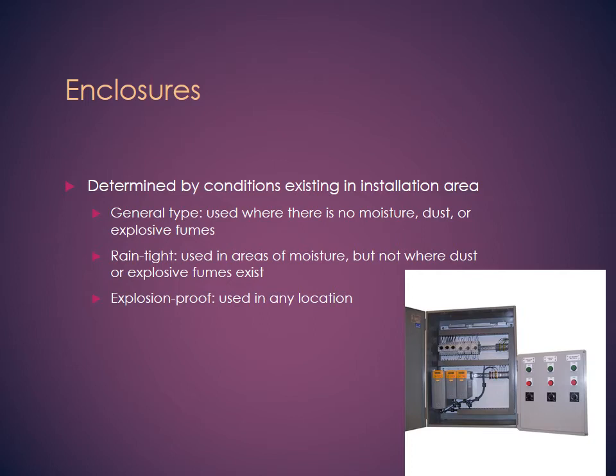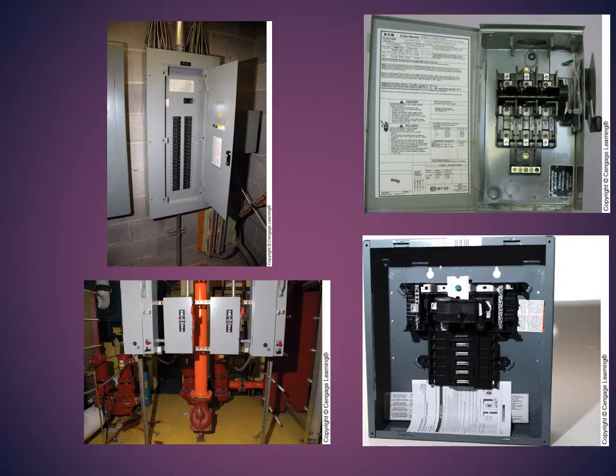If we work in a power plant and we have a gas leak, we might want leak proof containers that cannot have any water or gas going inside, because if you notice, there's a lot of control included inside the enclosures. Also, there's rain tight, which is for when it's going to be outside. Again, explosion proof is for locations where there are gas leaks and a possibility of fire or explosion, for example, a power plant.